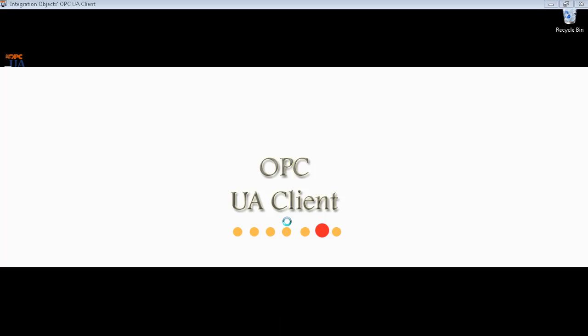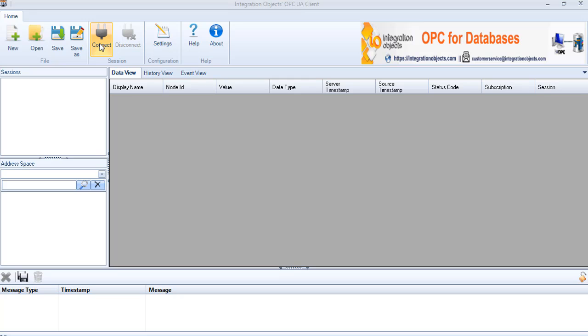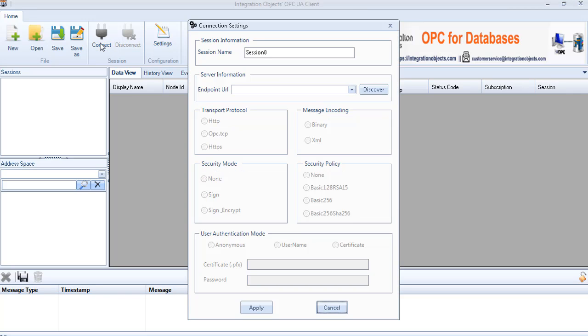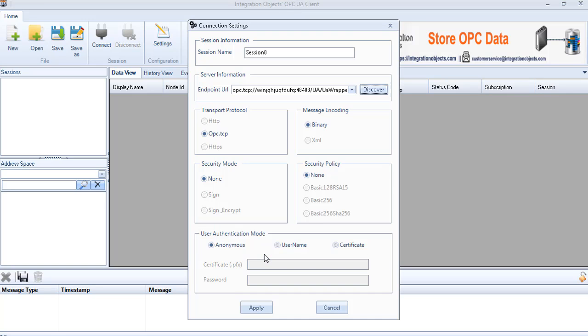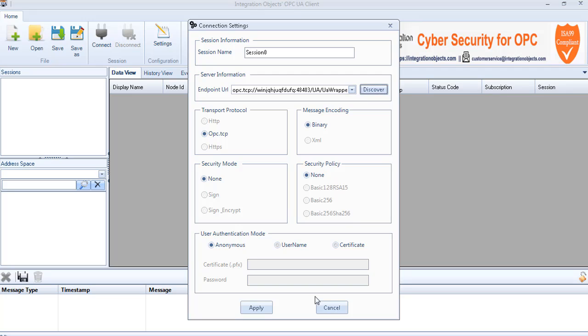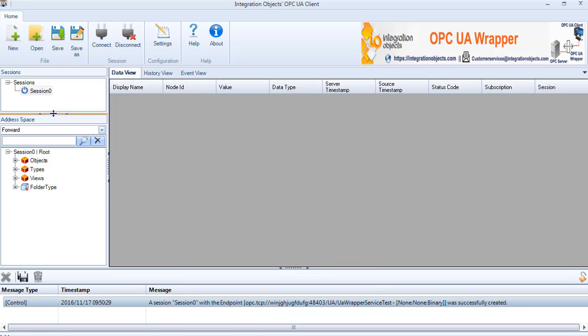Open the OPC UA client and click on the connect button in the menu bar. In the connection settings dialog, click Discover to browse the UA endpoint and select the created wrapper URL. You can choose OPC TCP protocol or HTTP protocol. Configure the connection and a session with the wrapper will be created.